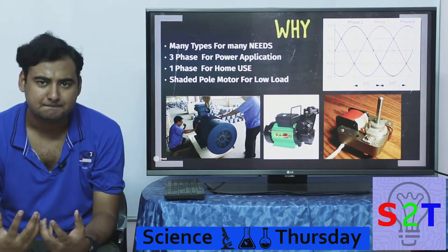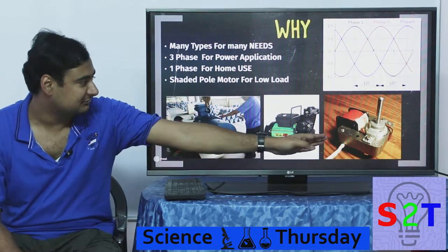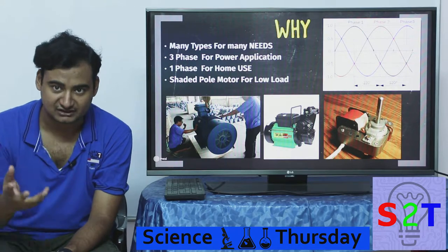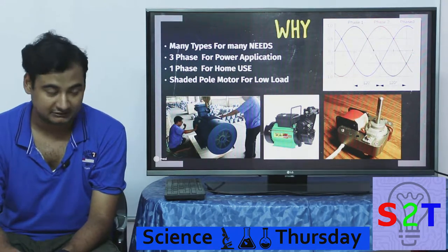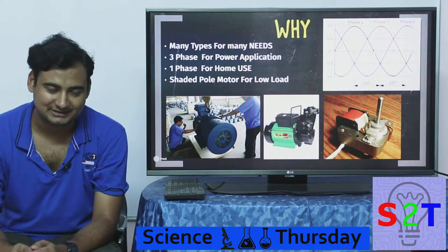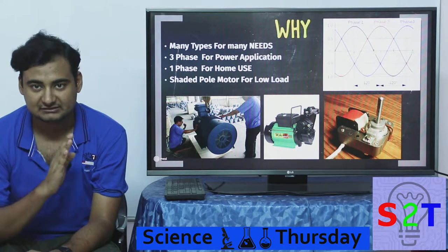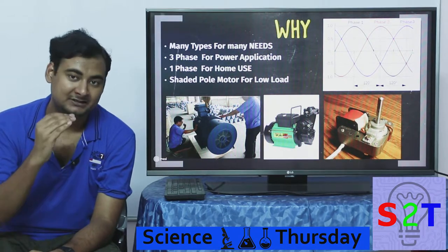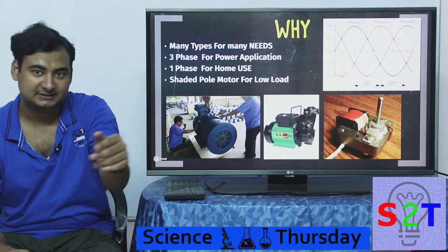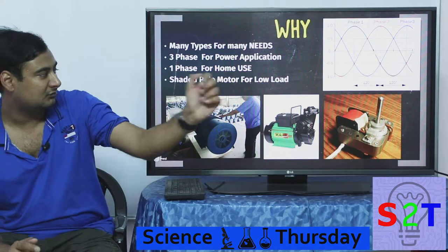There are many types of motors. Let's begin with the simplest one, which we call the shaded pole motor. It's generally used for very low torque needs — basically running fans. You will easily find them in microwave exhaust fans. Instead of using a capacitor, they have what's called a shaded pole: a small short coil that creates a sort of phase delay. This gives it rotational energy to start, and once it starts going you don't have to worry about it. It is self-starting, can run for decades, and is very simple and effective.